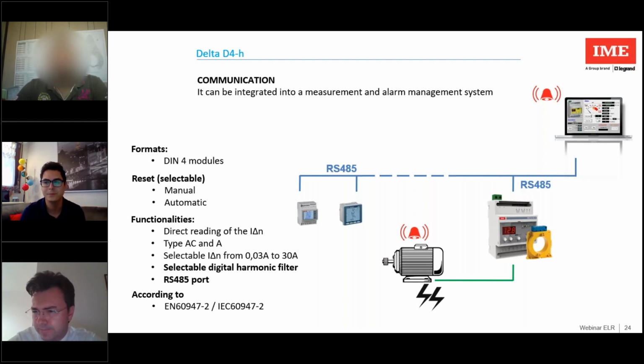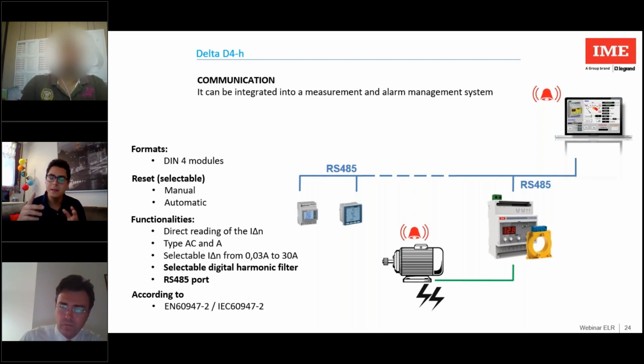Okay. From Hussam, how does it work with motorized MCCB and RCB? The relay is only a chip, only a contact that opens or closes, depending on how the MCCB or RCB works. When you have normally open or normally closed and you reach the threshold of your current differential relay that you set, it opens or closes the alarm. This goes to a coil, a minimum voltage coil or a launch current coil, and this operates the MCCB or RCB.